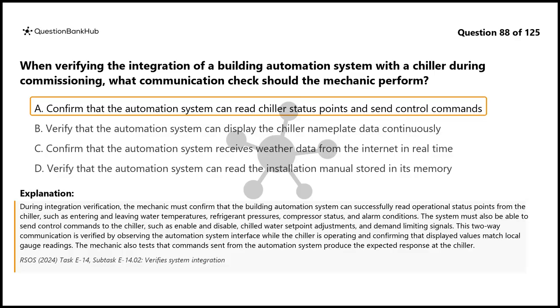This two-way communication is verified by observing the automation system interface while the chiller is operating and confirming that displayed values match local gauge readings. The mechanic also tests that commands sent from the automation system produce the expected response at the chiller.